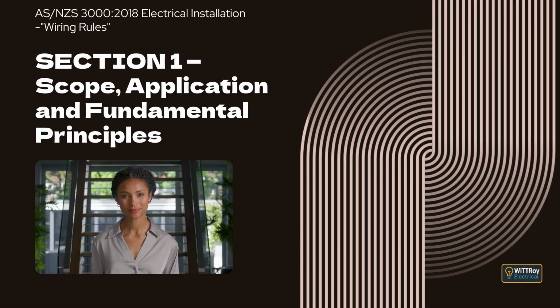Clause 1.5.5.5 is about electrical separation. Electrical separation means using an isolated transformer to supply one individual circuit. Because the active and neutral are not connected to earth anywhere, there is no return path through earth if a person touches one live part. This reduces the risk of electric shock. But this only works if the separated circuit stays completely isolated. It cannot be earthed, bonded, or connected to any other circuit.